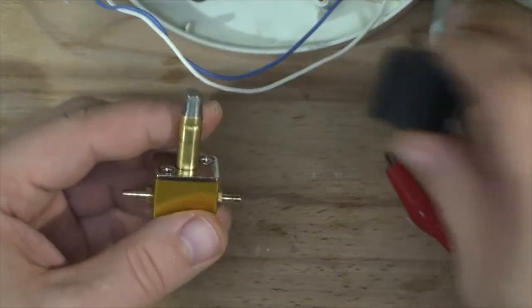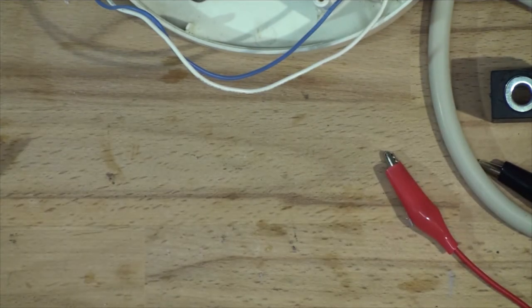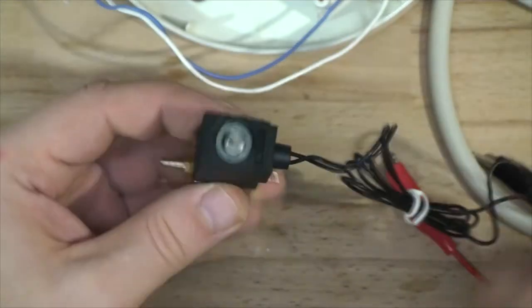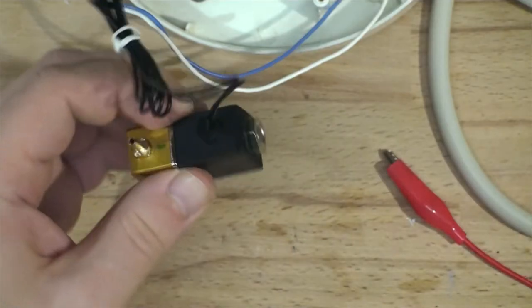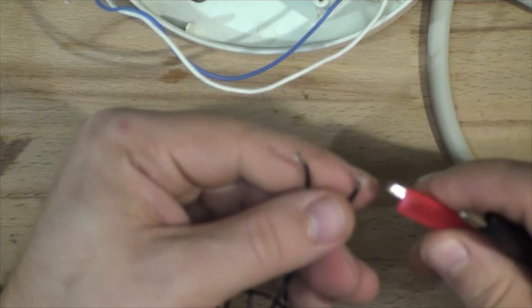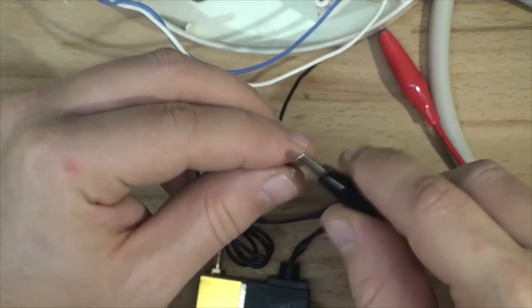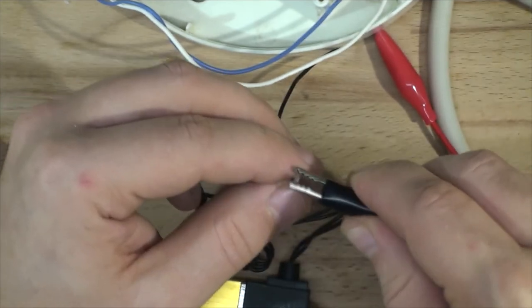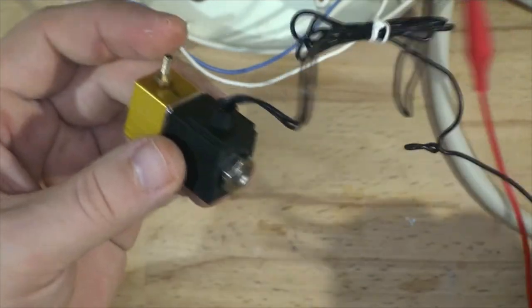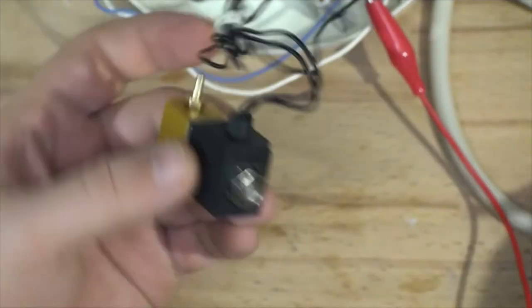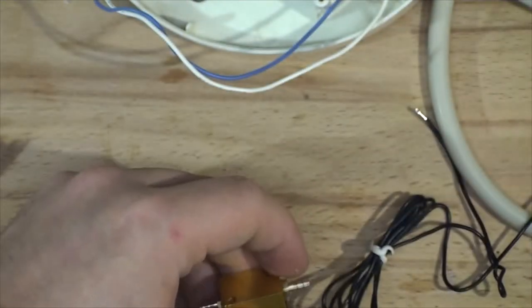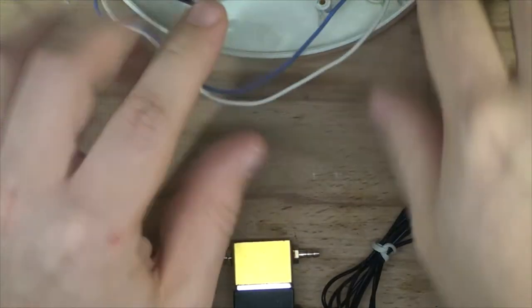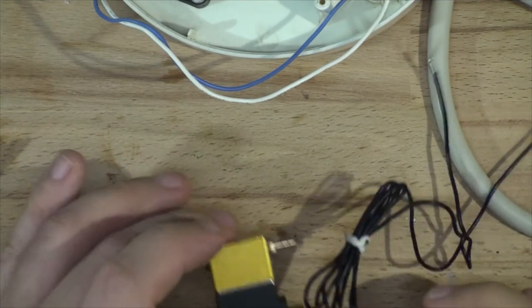Let's blow in it just to verify. Yep, it's sealed. So let's add the coil. Let's try powering it on, see how well it works. We've got 24 volt DC. I'm going to energize it and blow through it. You can hear it clearly. Air is coming out of it, which it didn't before. And of course now it's closed. So the valve is fixed. I will be blowing through this assembly just to make sure there's no clogs inside there.